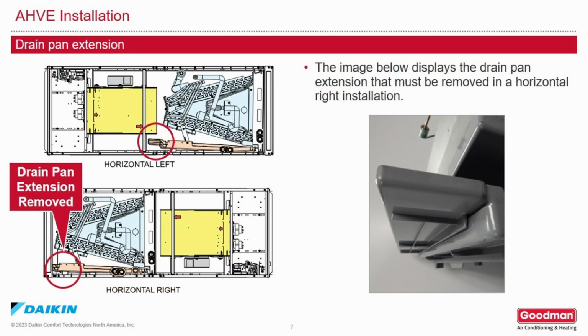The drain pan extension when installing the air handler in a horizontal orientation. When installing in a horizontal left orientation, the drain pan extension may stay on the pan. When installing in a horizontal right orientation, the drain pan extension must be removed.